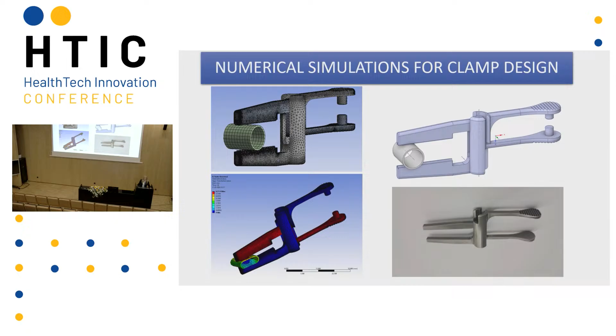This is the principle of action for laparoscopic instruments. Also we are relying on the idea that the clamping forces should be parallel on the whole working surface of the instrument. Within this project, we are working on reduced tissue traumatization, so we also developed an atraumatic insert. The atraumatic insert consists of two layers. The lower layer is built of titanium alloy. Actually, the whole instrument is built of titanium alloy.